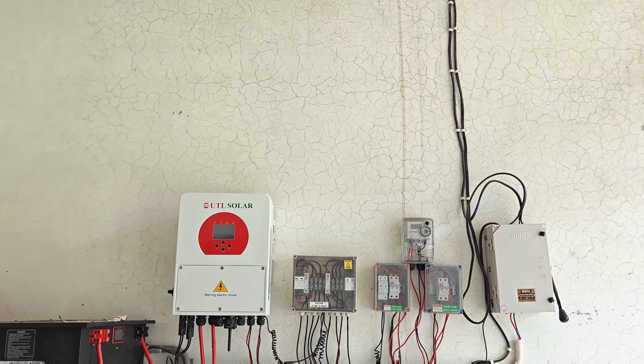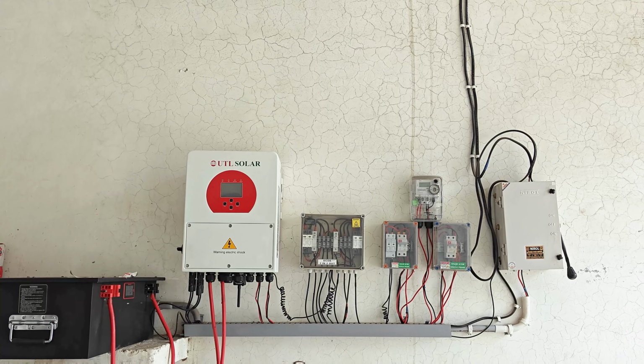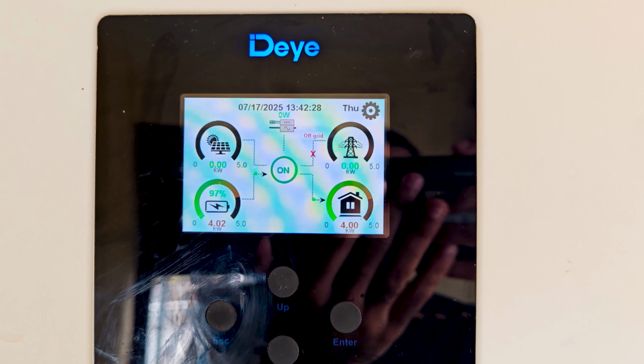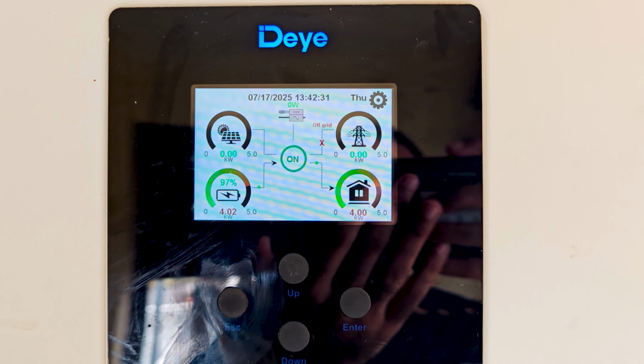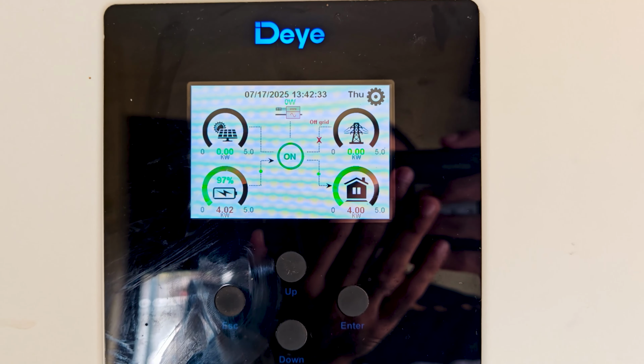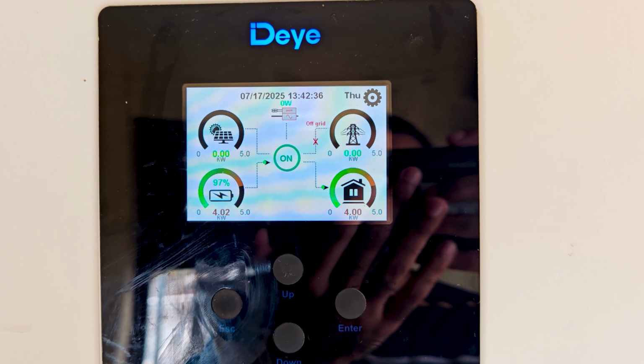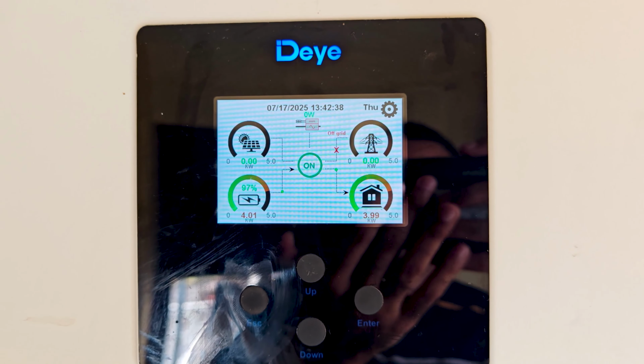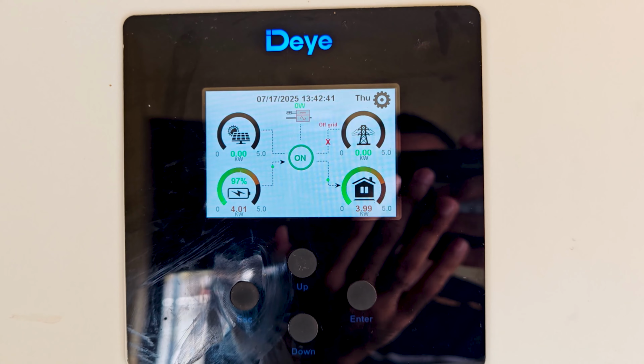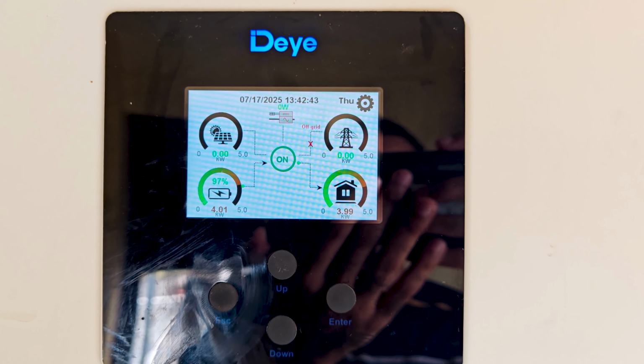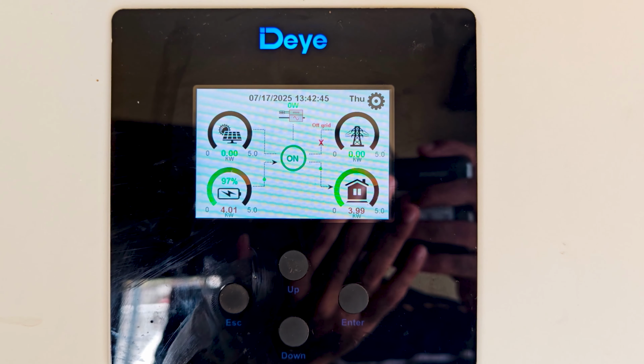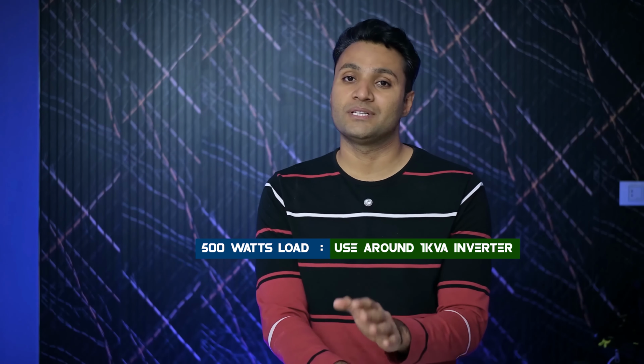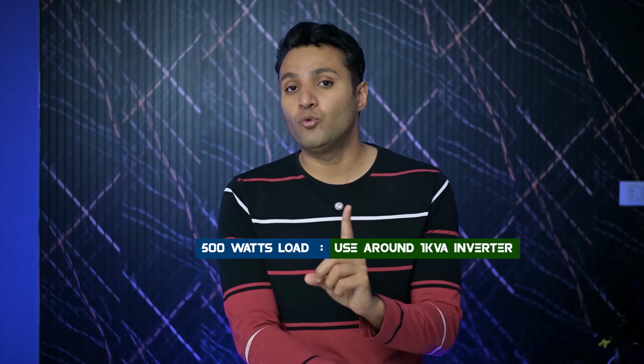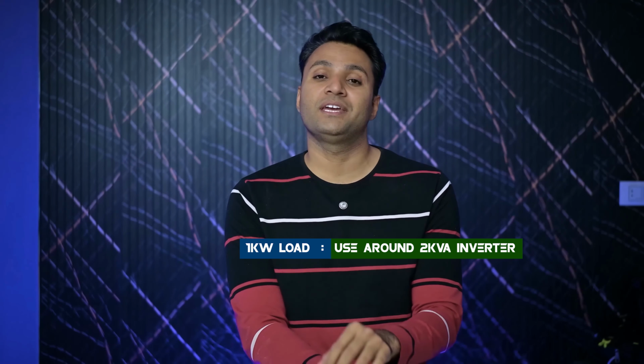Similarly, if you go with transformerless technology, then the same inverter can handle much higher load because transformerless technology gives you an almost 1 power factor. That means if you have a 5 kVA inverter, then it can handle a full 5 kilowatt load. So if you want to calculate VA and you are planning to buy normal company inverters, then whatever formula you use, always keep at least 50% margin. For example, if you want to run a 500 watt load, then you should use a 1 kVA inverter. Only then you will be able to run that 500 watt load comfortably.